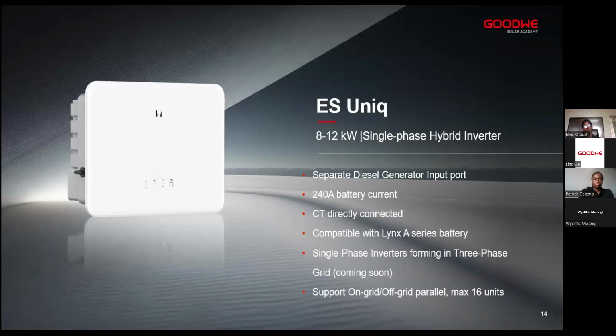I'll just run through our ES Uniq, which is our newest inverter in terms of the single phase low voltage. It is in the sizes of 8, 10, and 12. Then one major technical thing that it has is that it has a separate diesel generator input. Therefore, you have the grid inputs, then the diesel generator inputs. Then it is compatible with our Lynx A battery, which I'll mention in a few. Then it supports on and off grid parallelly up to 16 units.